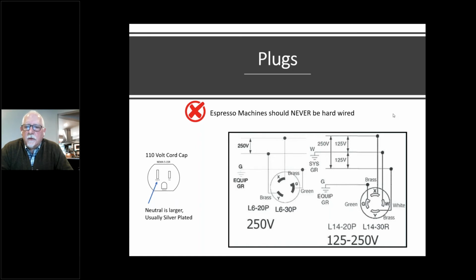For most 110 volt plugs, for the smaller machines, the plug you're going to see on the left is what you run into. It's important that the neutral wire, the white wire or the blue wire, depending on how you're doing it, go to the neutral. And that neutral is a bigger leg. Sometimes it's silver. And the reason for that is because inside the machine, all the switching that it's going to do, it's going to be switching the hot leg. It doesn't want to switch the neutral. So it's going to expect that hot leg come from that smaller prong.